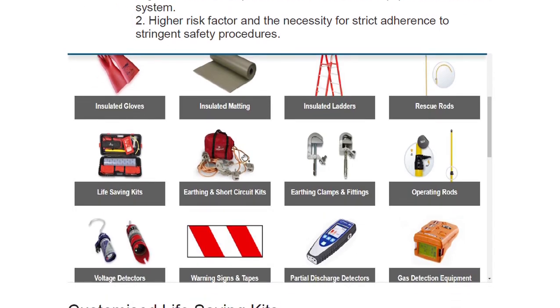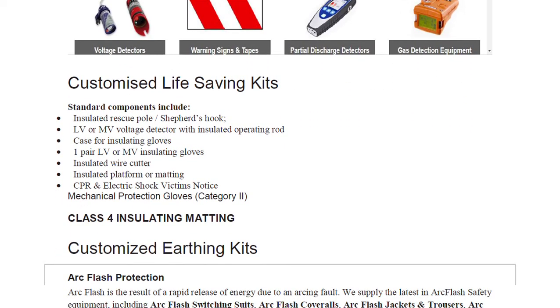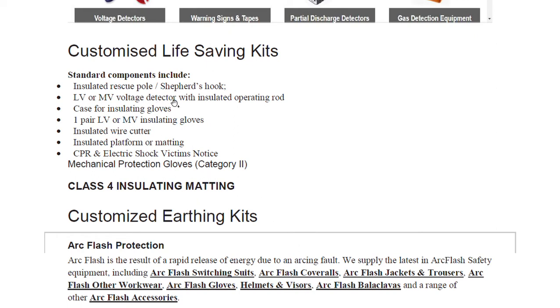Safety items include: insulated gloves, insulated matting, insulated ladders, rescue hooks, life saving kits, earthing and short circuit kits, earthing clamps and fittings, operating rods, voltage detectors, warning signs, partial discharge detectors, and gas detection equipment. Customized life saving kits include insulated rescue pole, Shepherd's hook, low voltage or medium voltage detector with insulated operating rod, one pair of low and medium voltage insulating gloves, insulated wire cutter, insulated platform or matting, CPR electric shock victim notice, and mechanical protection gloves.